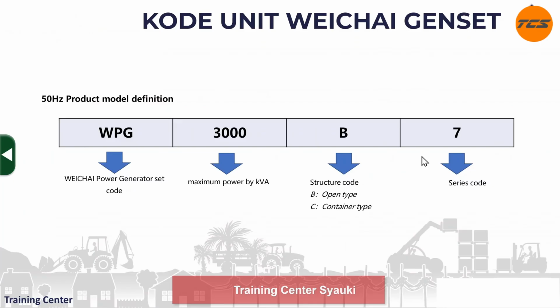Next, this is how to read the unit code. For example, WPG stands for Weichai Power Generator Set. 3000 indicates the maximum power rating of the unit in kVA. The letter B indicates an open type unit. If the letter C appears, it means a container type unit. The letter F stands for frame-mounted fuel tank. The number 7 represents the series code, indicating how many times the unit design has been updated or modified.